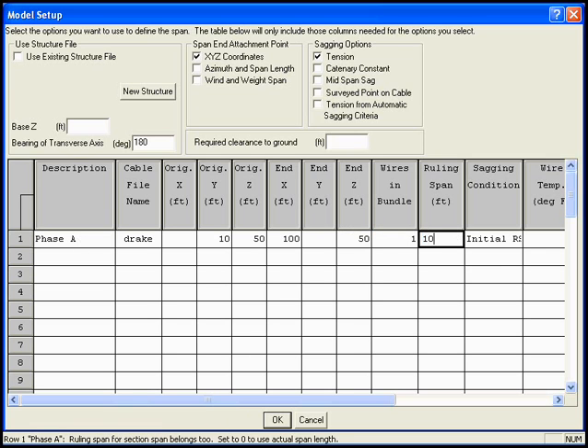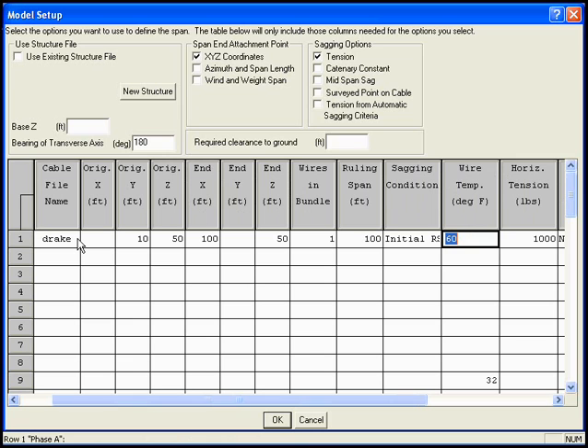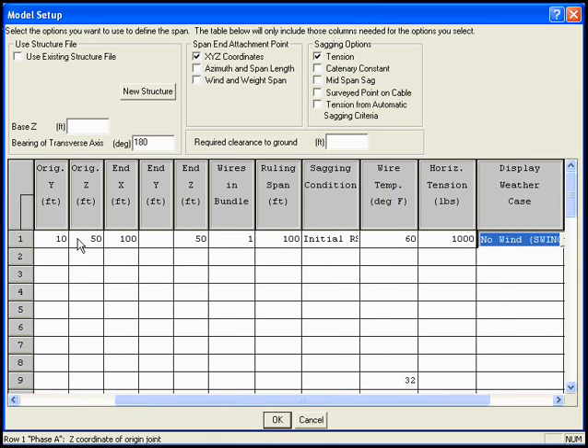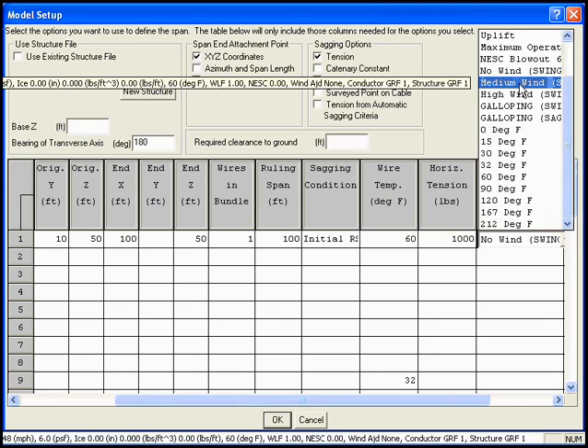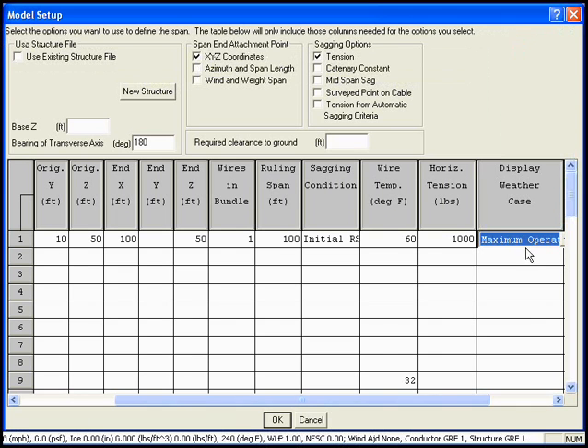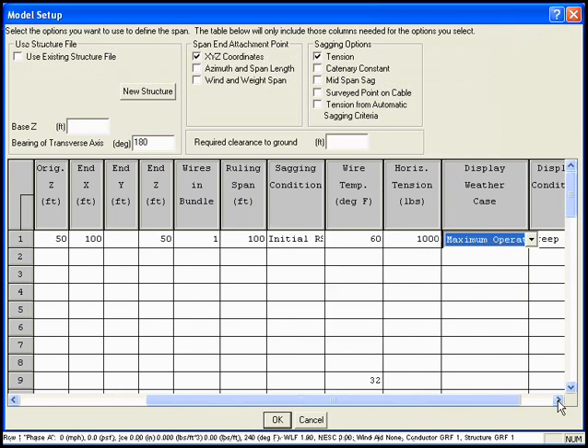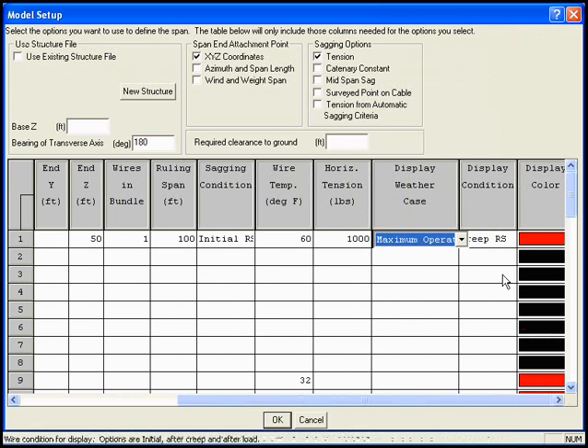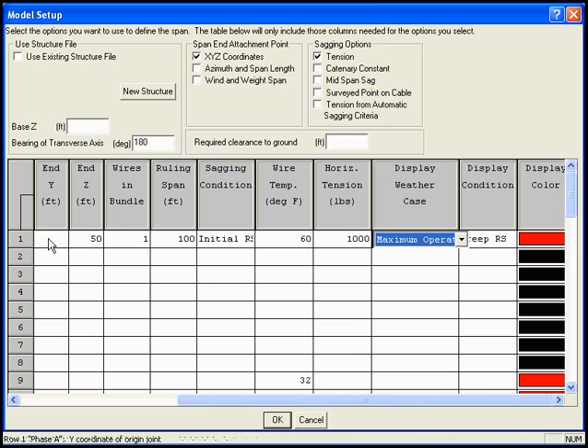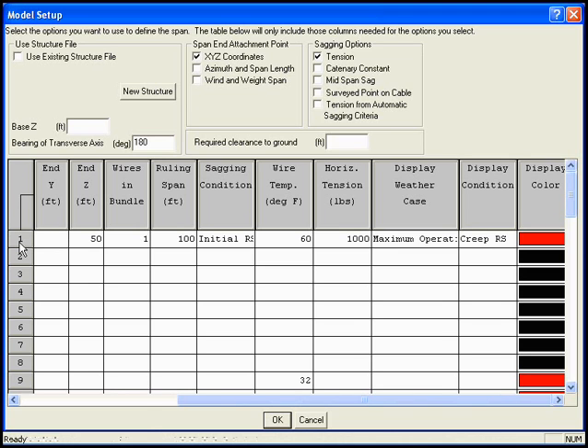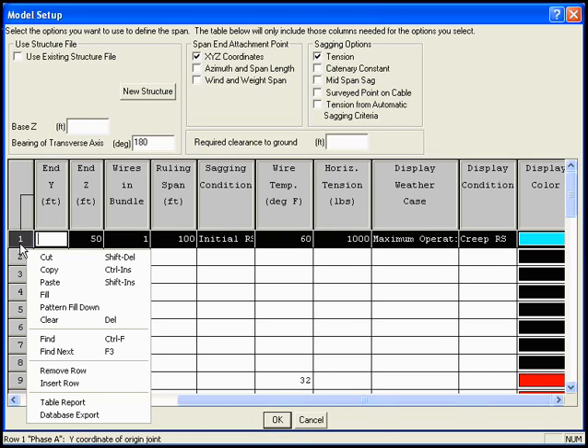We'll use a ruling span of 100 feet. We'll sag it in with the initial ruling span method at 60 degrees, and we'll leave it at 1,000 pounds. And finally, we'll want to show this at our maximum operating temperature, and we'll want to show it after creep.